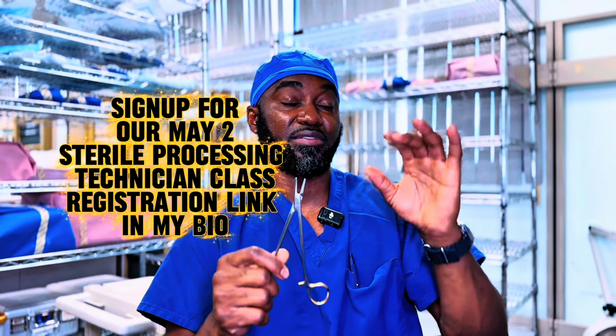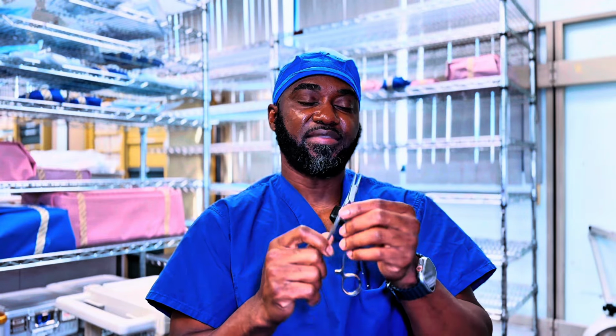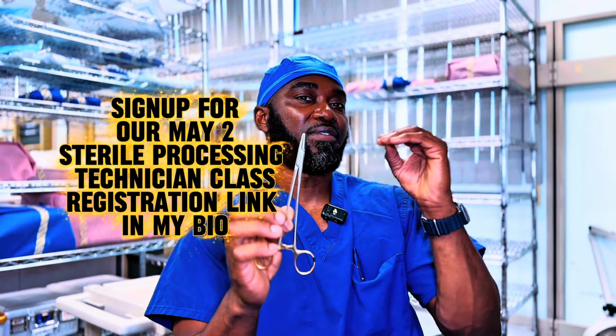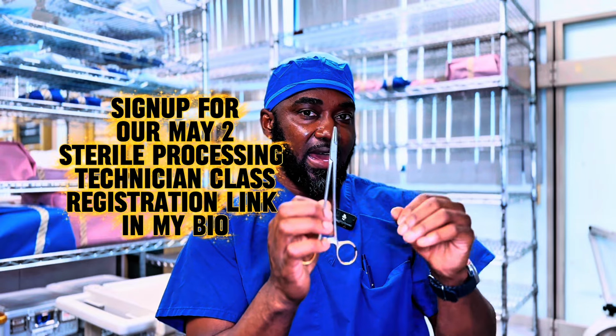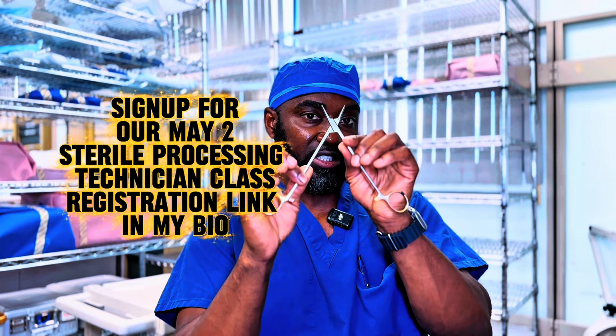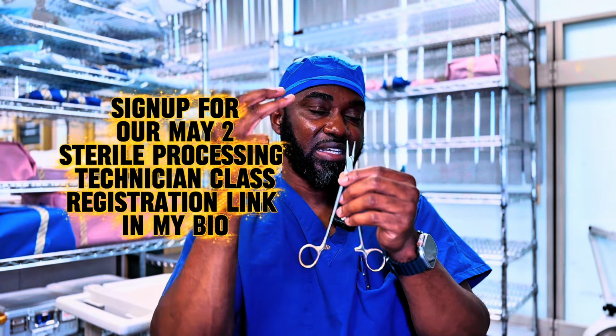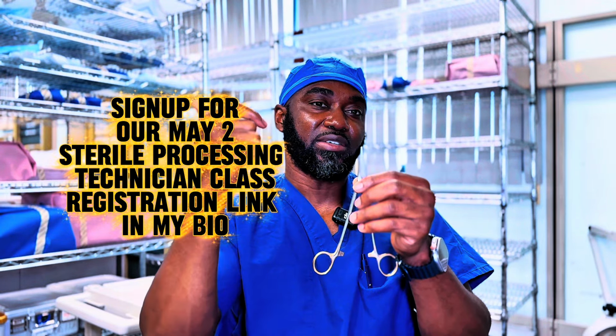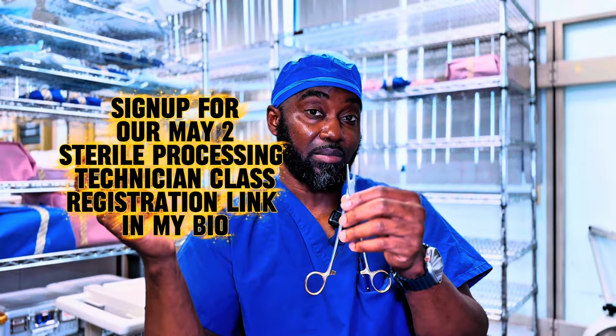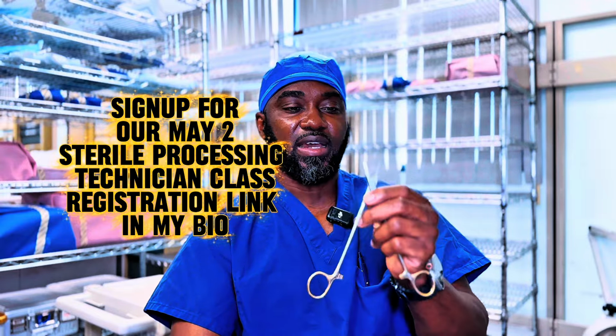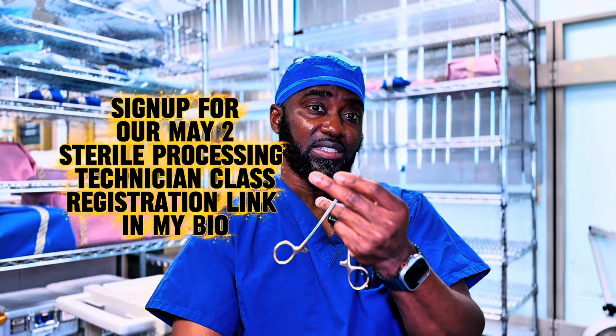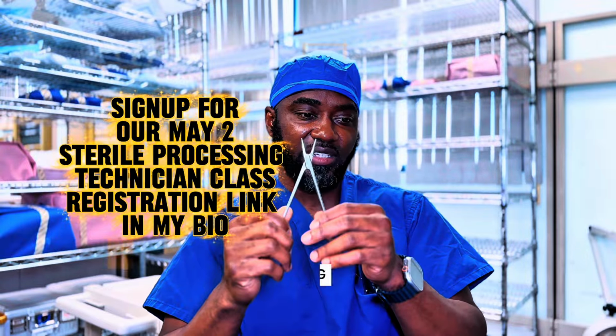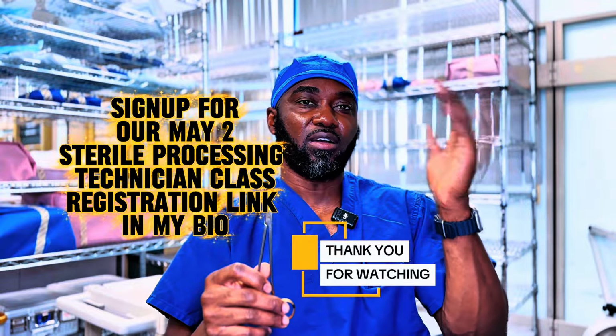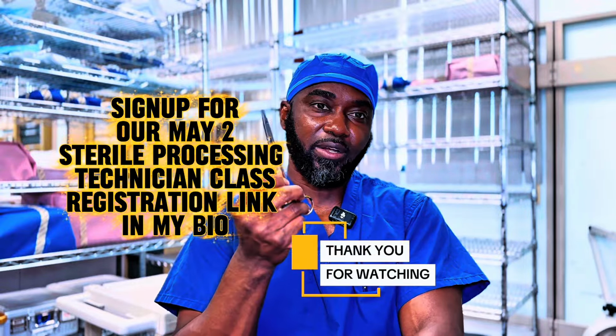That's the difference between the validation process, which is carried out by manufacturers, and the verification process, which is carried out by the end user. We are only following what was done in the lab to make sure that microbes on this instrument were killed, using the same packaging method, the same sterilization cycle, but at double the time of the sterilization. Hopefully that helps break down the validation process and verification process of medical devices as they go through the 510K or pre-market approval phases for medical instrumentation.